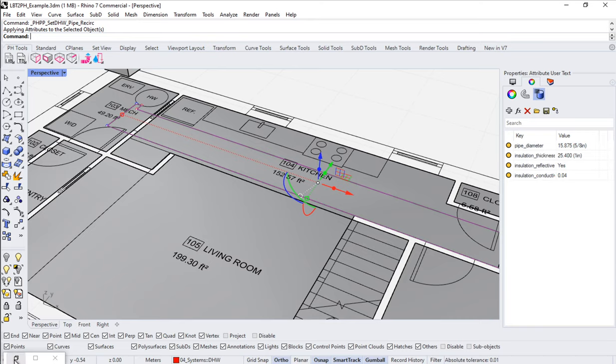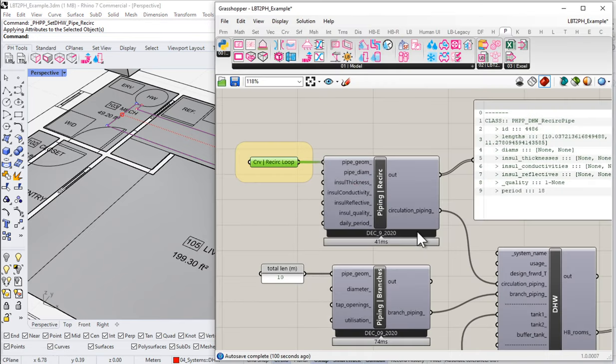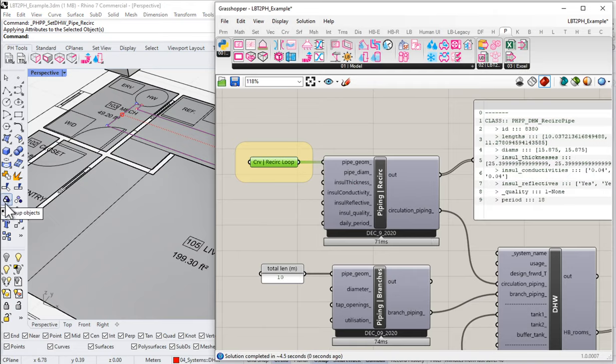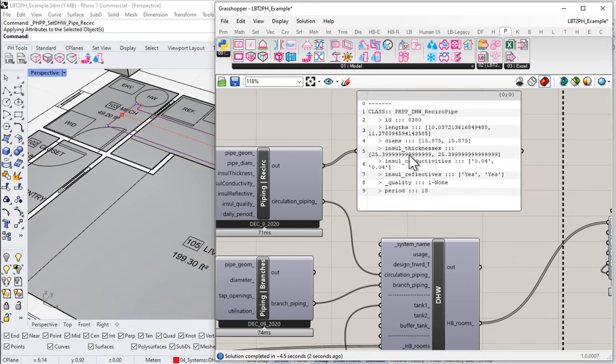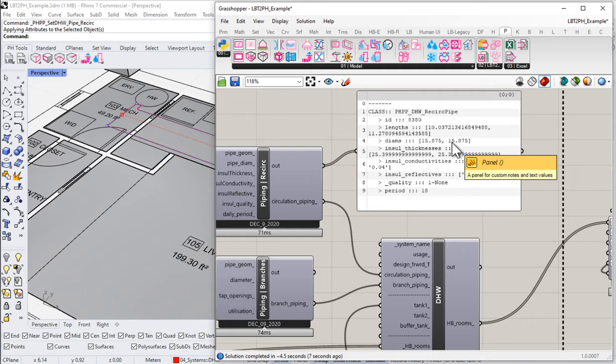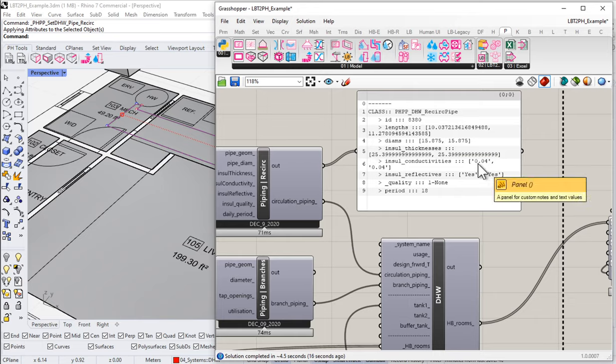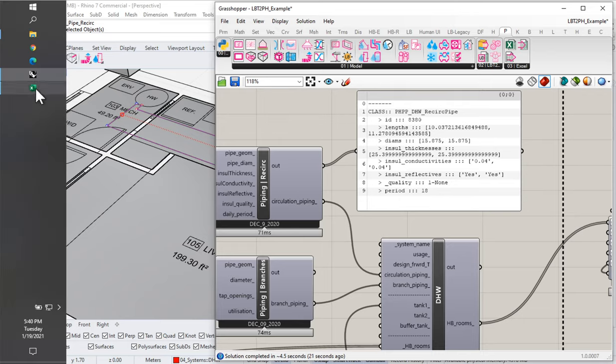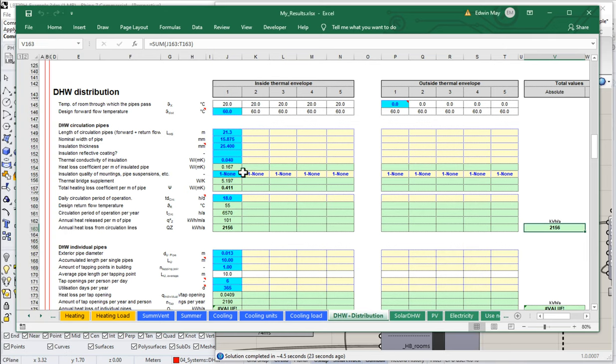When I do that, just as we've seen many times before with attribute user text, that information gets logged or saved onto the geometry. Now if I come back into my Grasshopper scene and push that geometry through, it should be smart enough to go to Rhino, calculate all the lengths, and read all of those parameters off of the Rhino geometry. And notice we're now getting our thicknesses: five-eighths of an inch, insulation thickness of an inch, conductivity 0.04, and reflectiveness yes. So how did that affect our PHPP? All of that information is flowing through into our circulation loop now.